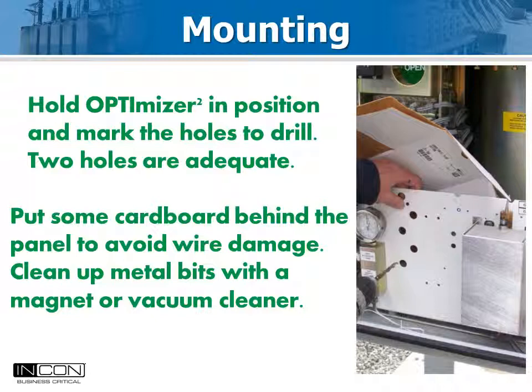Mounting the Optimizer 2 is easy. Often it is possible to place it behind the window so it can be seen with the door closed. Field crews like this. When drilling, be careful not to nick wires that might be hidden behind the panel. Also, clean up the metal bits before you make gas connections to prevent impurities from getting into the gas system.